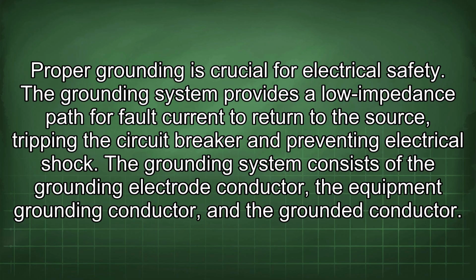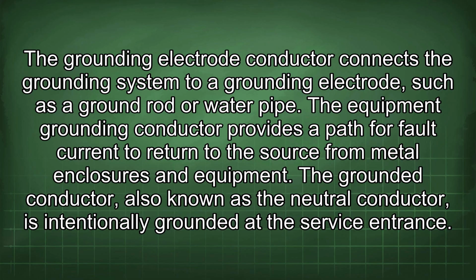The grounding system consists of the grounding electrode conductor, the equipment grounding conductor, and the grounded conductor. The grounding electrode conductor connects the grounding system to a grounding electrode, such as a ground rod or water pipe. The equipment grounding conductor provides a path for fault current to return to the source from metal enclosures and equipment. The grounded conductor, also known as the neutral conductor, is intentionally grounded at the service entrance.